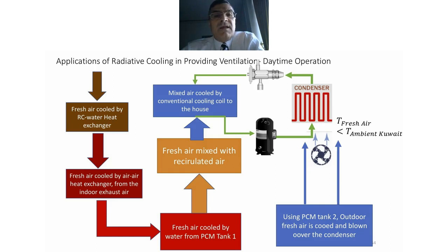As for the cold tank, tank 2, it is used to pre-cool the air entering the condenser of the air conditioning system to enhance its COP at peak time. So this is really where the application is. When the outdoor temperature is higher than the PCM2, the PCM2 would cool the air and the air will go over the condenser. So here we have two different applications, as I mentioned before, one for the ventilation and one for the COP.